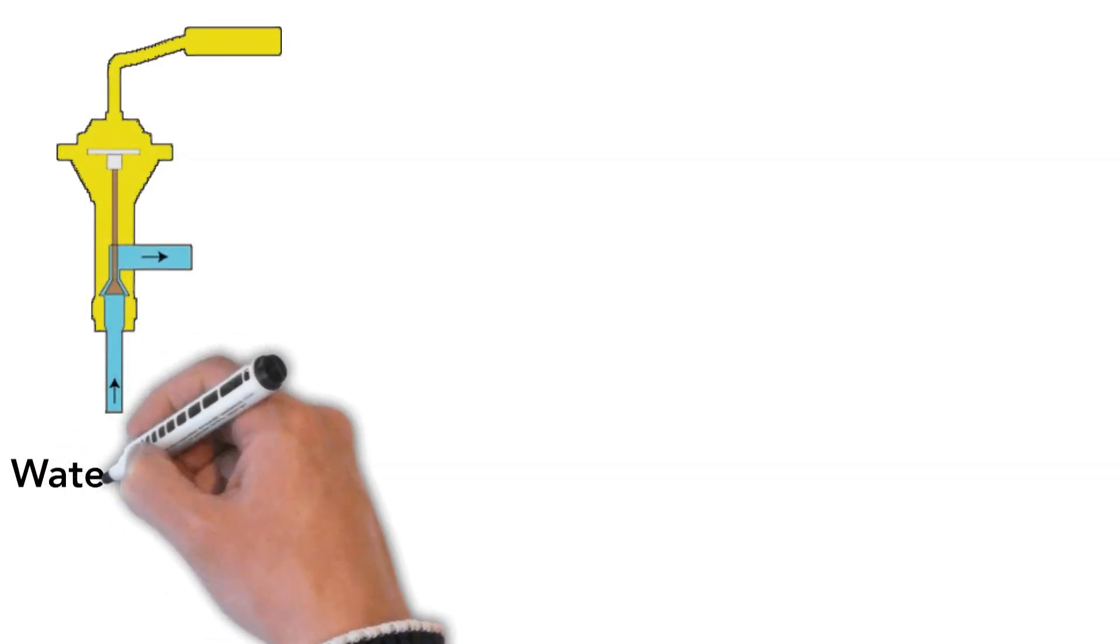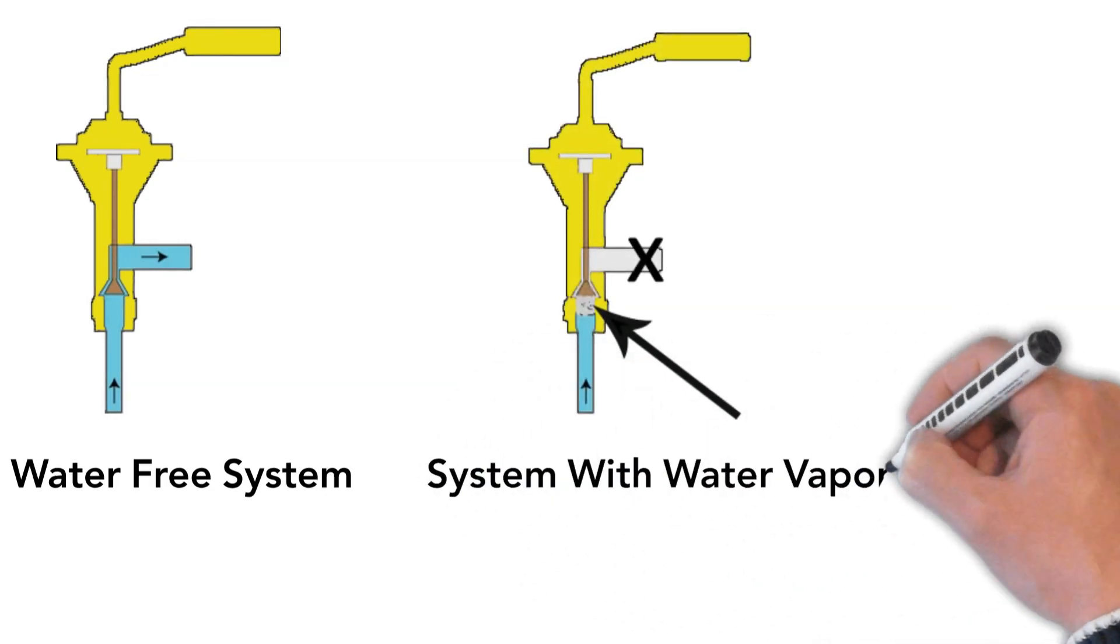Water vapor must be removed from HVAC systems for several reasons. Water vapor can freeze up at the expansion devices, such as thermal expansion valves and capillary tubes, causing a complete loss of the cooling effect.